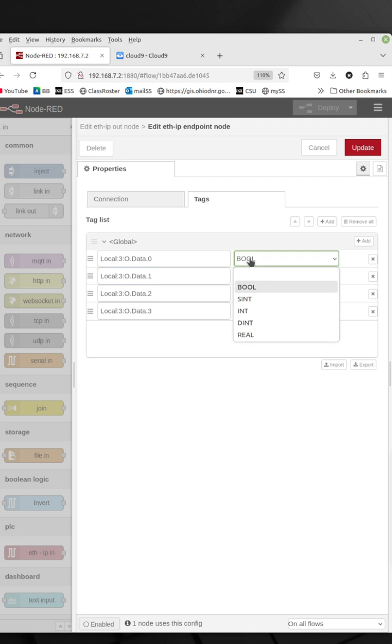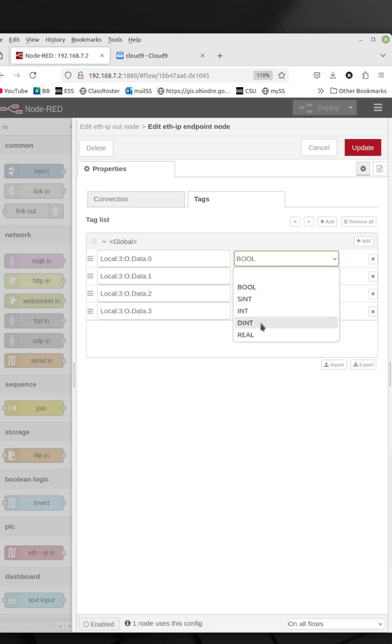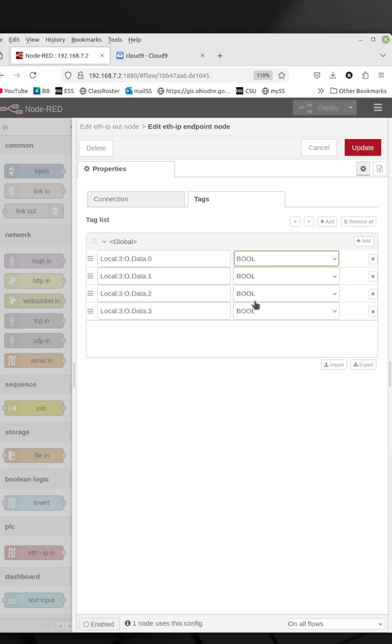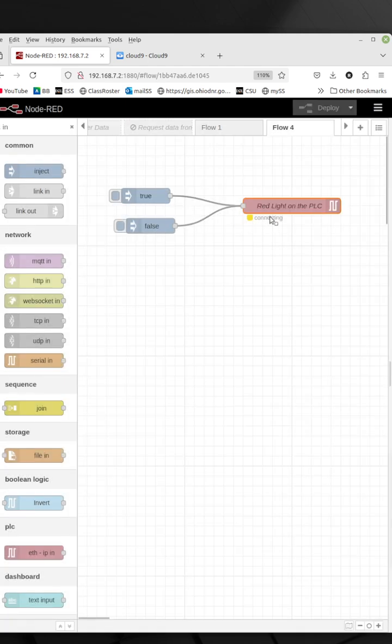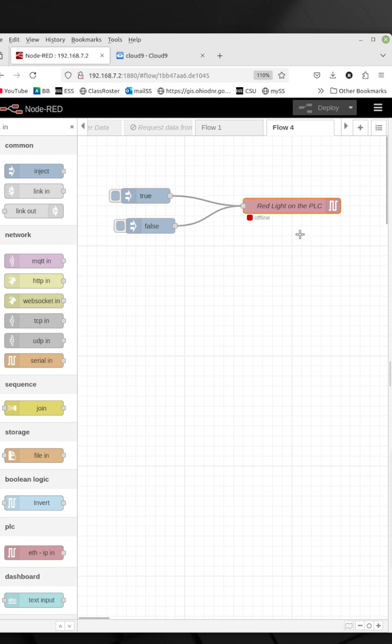Or if you're not doing Boolean and you're sending an integer, you've got to know whether it's an integer or a double int or if it's a real type tag. So the tags, all of this must be correct. If it doesn't, you will see this error or offline show up here in red. If everything is correct and you're online and the PLC is working, you will see it turn green and it will say online.